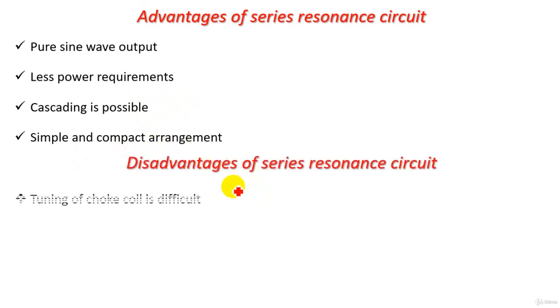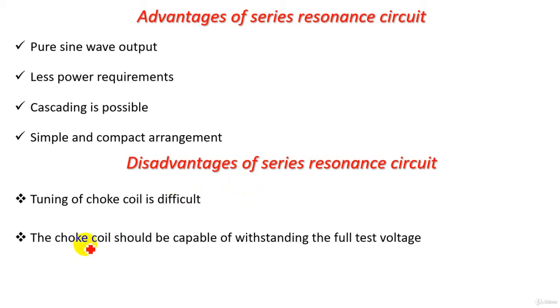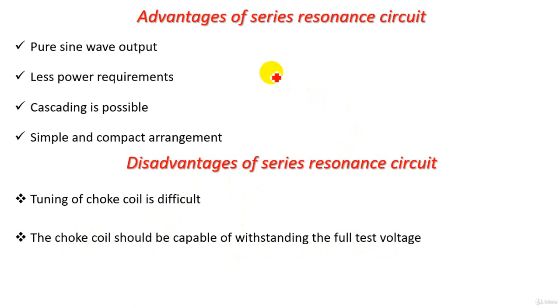Disadvantages of the series resonance circuit: Tuning of the choke coil is difficult — adjusting the coil to make resonance occur is challenging. Also, the choke coil must be capable of withstanding the full test voltage, requiring special specifications. This completes our understanding of the resonant transformer for producing high-voltage AC at power frequency.